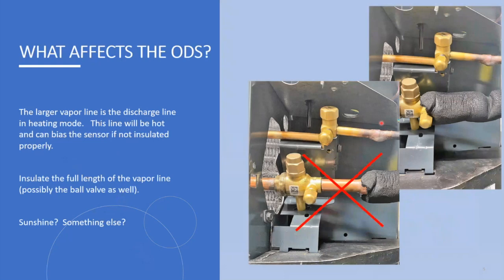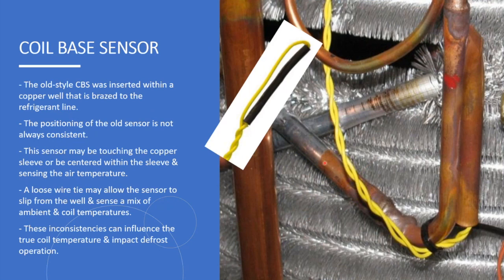One thing to consider is that the outdoor ambient sensor does play a big part in whether it decides to defrost or not. So you want to make sure that it's not in direct sunlight, it's not in front of a bathroom fan vent or something that's going to be affecting the temperature. Even having the insulation pulled back on your larger pipe, your vapor line, because that can be hot in heating mode, could affect this. Okay. So that works in conjunction with a coil sensor.